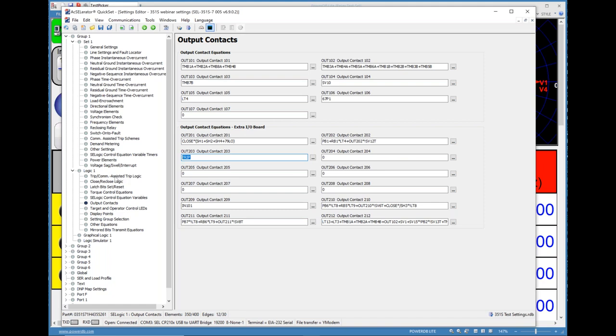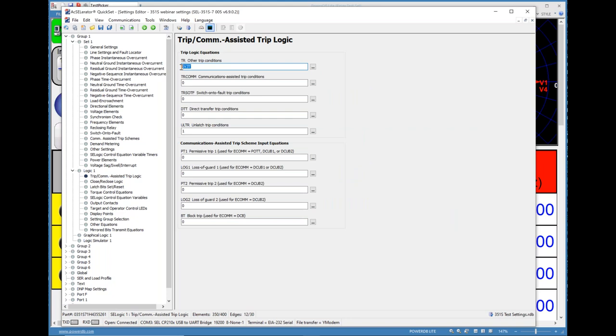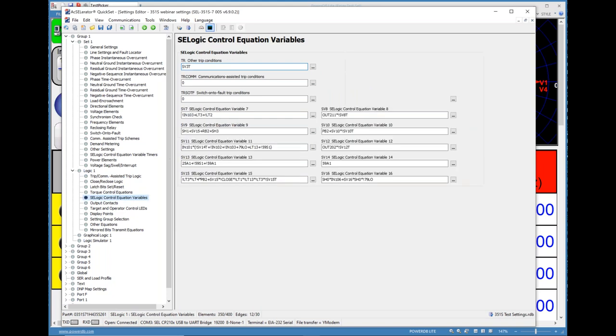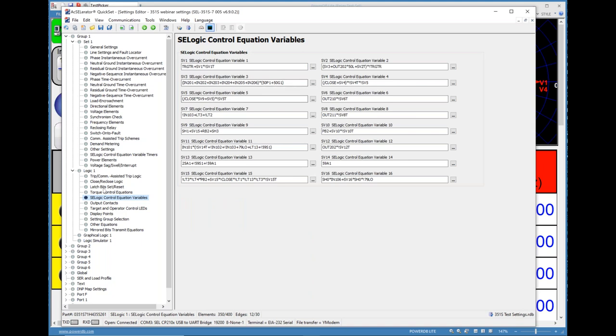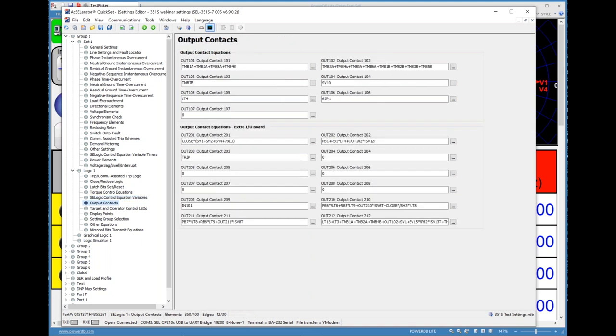That's how the logic equations work. They can get complex or very simple — this one is pretty simple, but they can get very involved. Today we're going to do element testing. We saw how the logic equation works and how the logic is different between a trip condition and an output condition. So today we're going to control the logic. Earlier I mentioned we're tied to OUT107 on the relay — OUT107 has nothing tied to it, no logic, zero. We want to come in and see how we can test these elements.